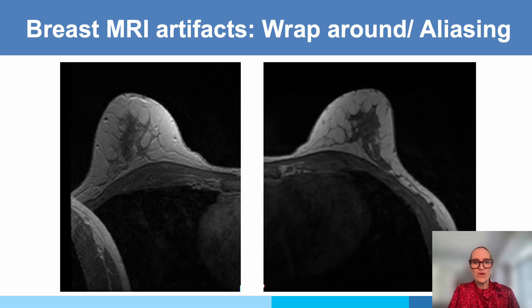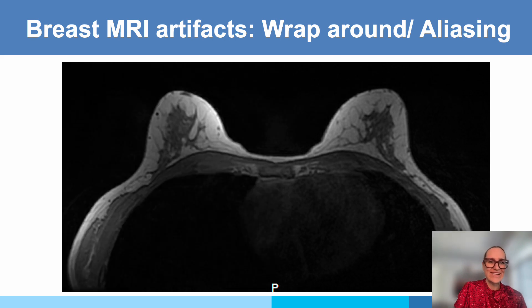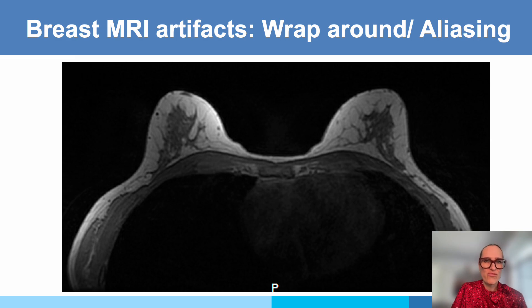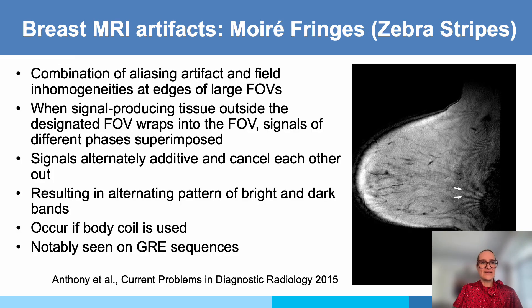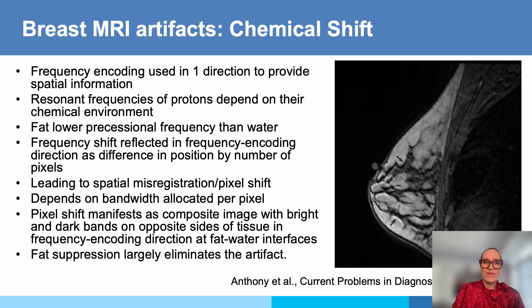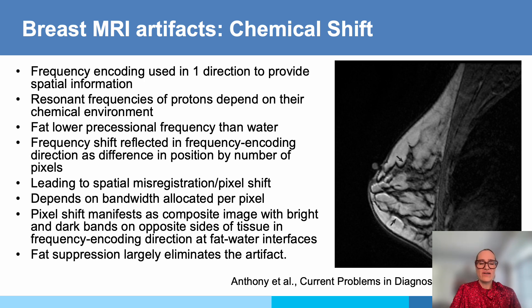Here is an example with wraparound, and here without — my technologist produced those images specifically for this video; the second is the ideal image you want to see. Zebra stripe artifacts are more historical, most notably on gradient echo sequences, and occur if the body coil is used, which we should not do. Chemical shift artifacts are also largely historical since fat suppression eliminates them; all of our protocols now use selective fat suppression, but if you are not using fat-suppressed images, be aware they can exist.